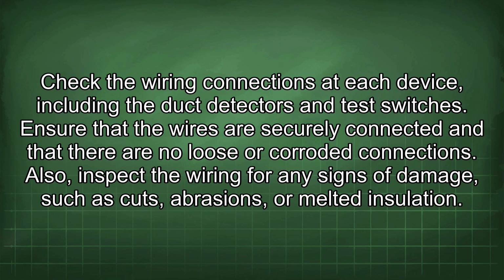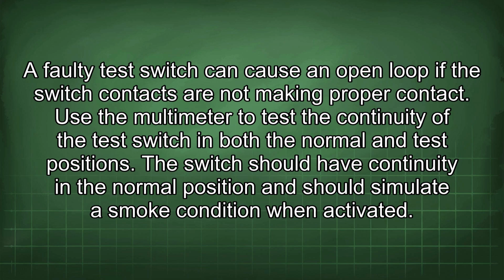Check the wiring connections at each device, including the duct detectors and test switches. Ensure that the wires are securely connected and that there are no loose or corroded connections. Also, inspect the wiring for any signs of damage, such as cuts, abrasions, or melted insulation. A faulty test switch can cause an open loop if the switch contacts are not making proper contact. Use the multimeter to test the continuity of the test switch in both the normal and test positions. The switch should have continuity in the normal position and should simulate a smoke condition when activated.